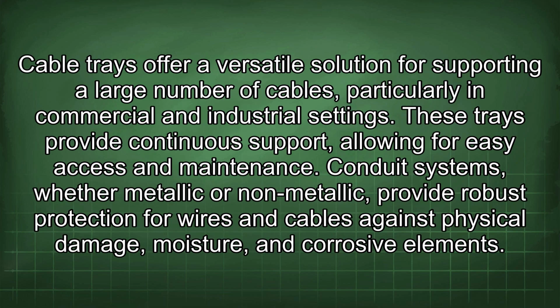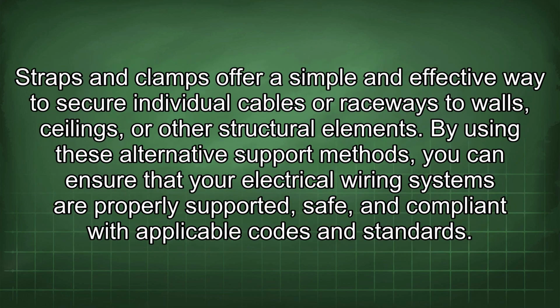purpose. Cable trays offer a versatile solution for supporting a large number of cables, particularly in commercial and industrial settings. These trays provide continuous support, allowing for easy access and maintenance. Conduit systems, whether metallic or non-metallic, provide robust protection for wires and cables against physical damage, moisture, and corrosive elements. Straps and clamps offer a simple and effective way to secure individual cables or raceways to walls, ceilings, or other structural elements. By using these alternative support methods, you can ensure that your electrical wiring systems are properly supported, safe, and compliant with applicable codes and standards.